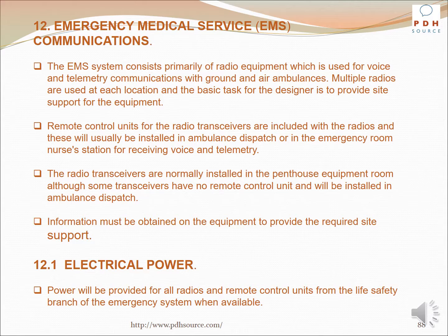The radio transceivers are normally installed in the penthouse equipment room, although some transceivers have no remote control unit and will be installed in ambulance support. Information shall be obtained on the equipment to provide the required site support. Power will be required for all radios and remote control units from the life safety branch of the emergency system when available.